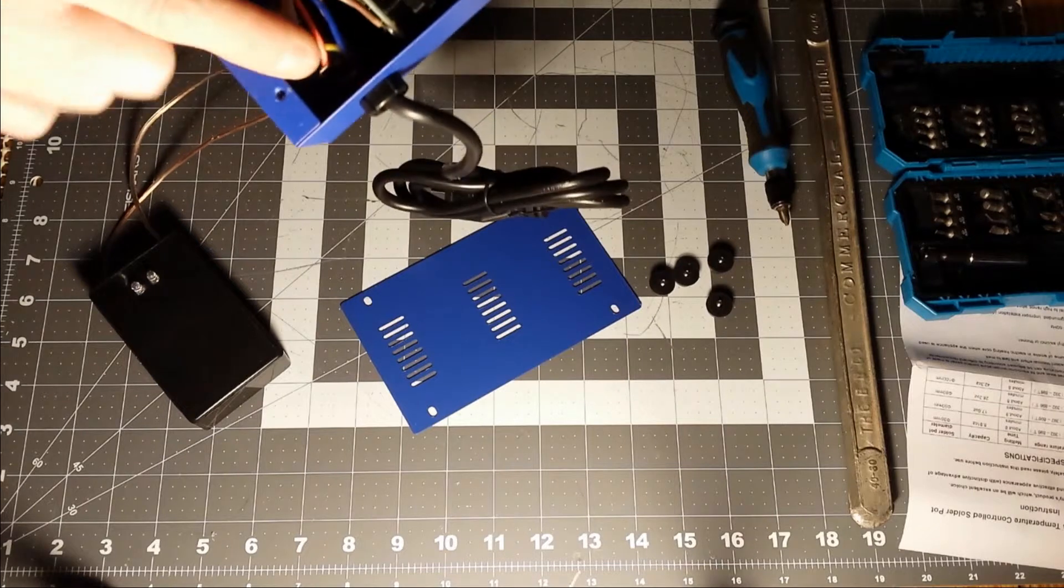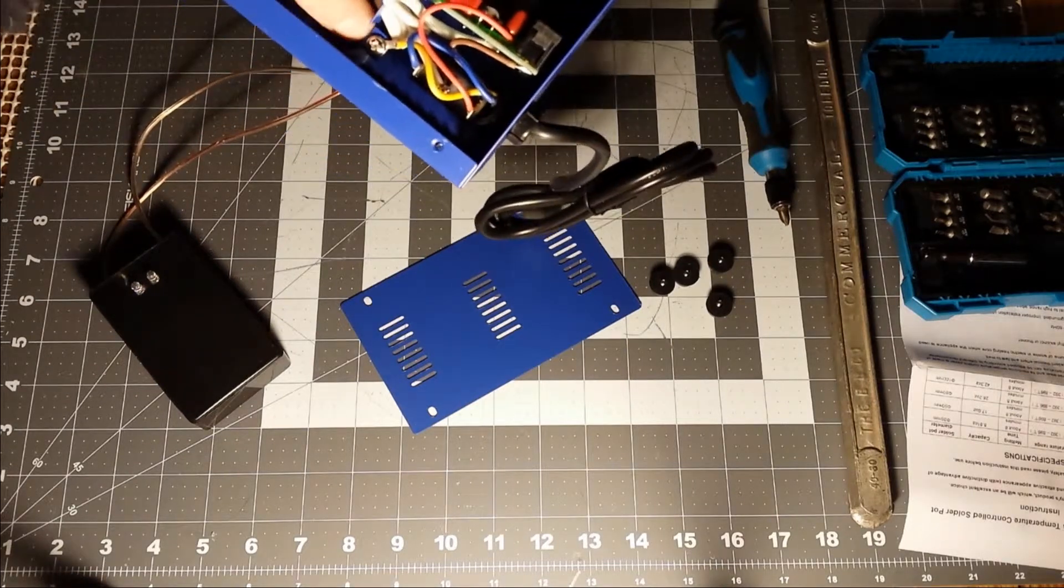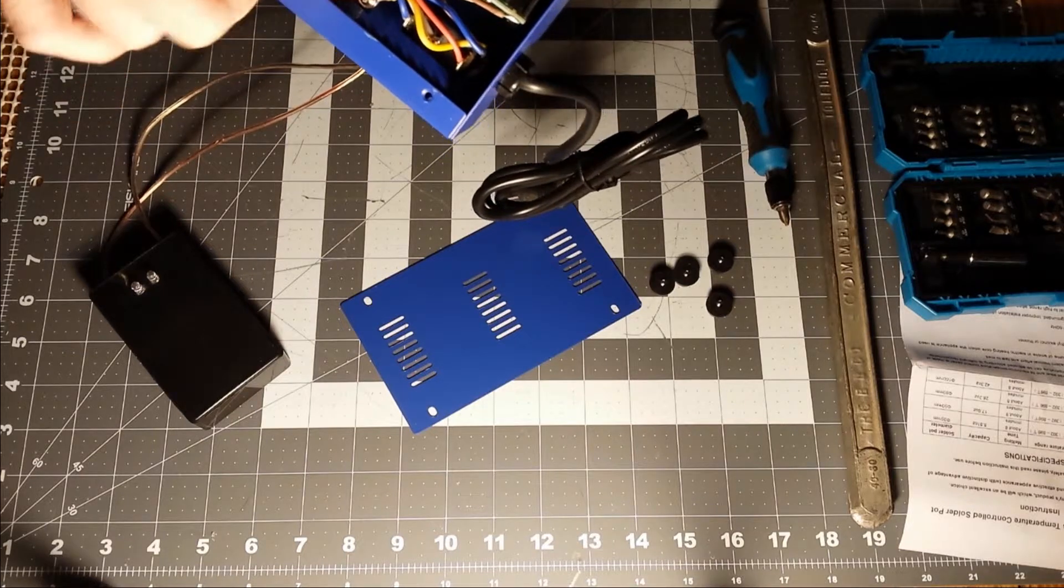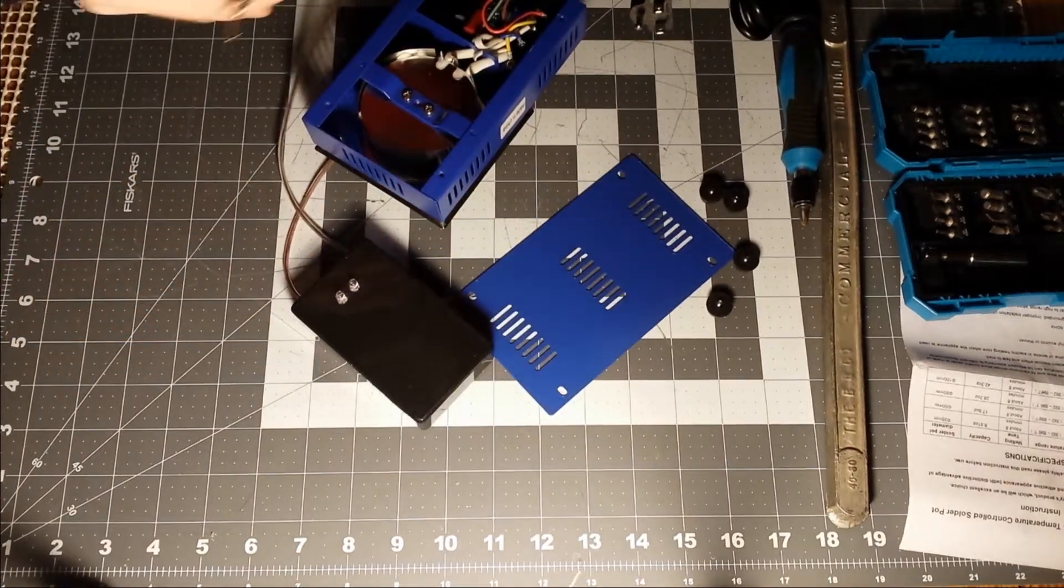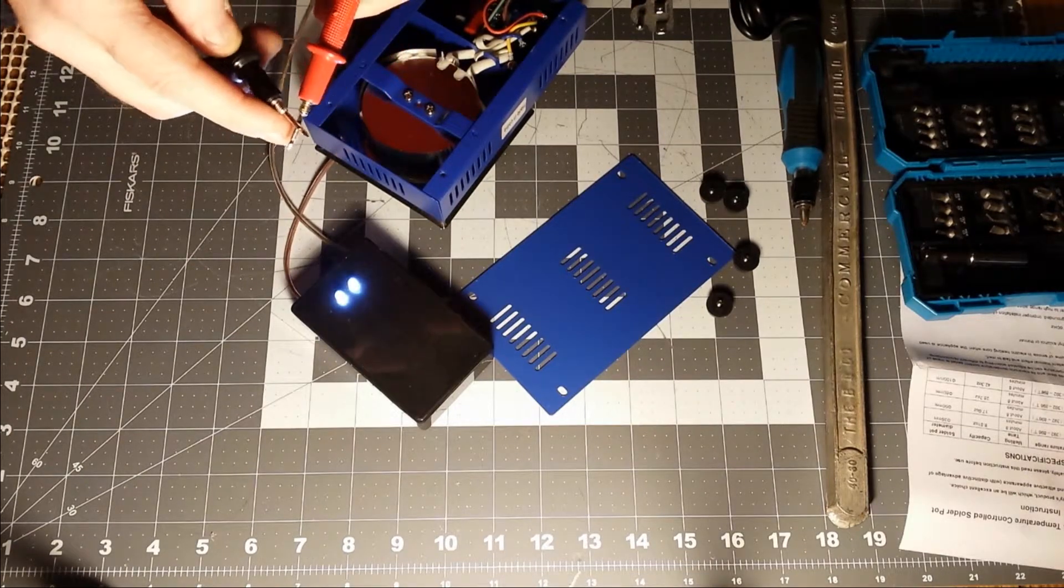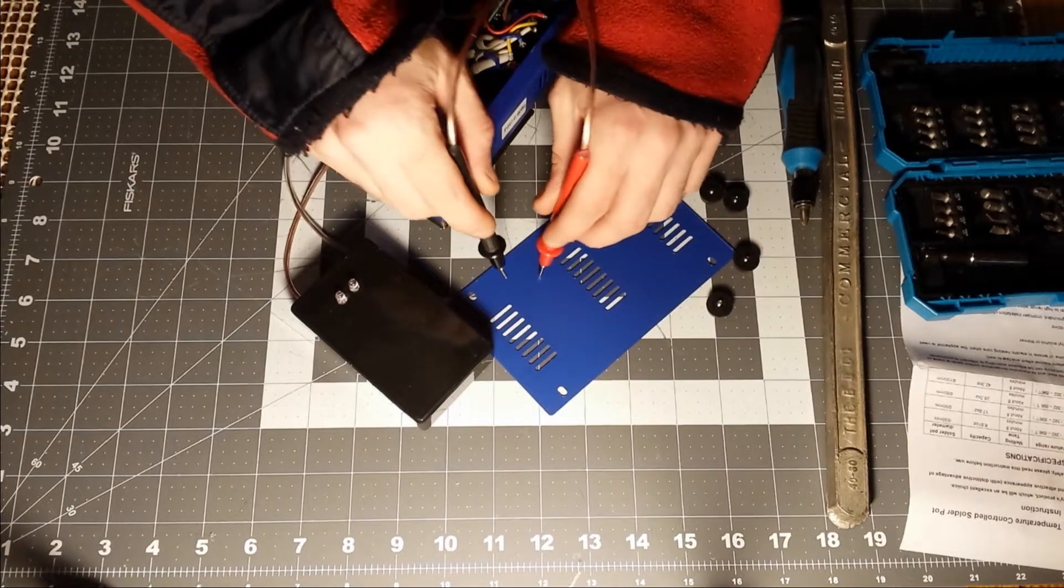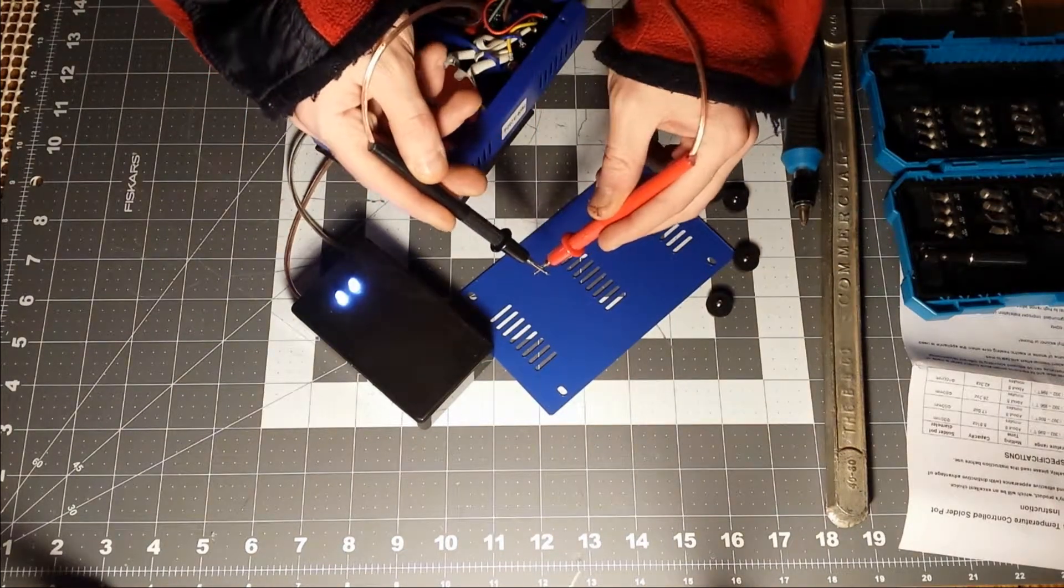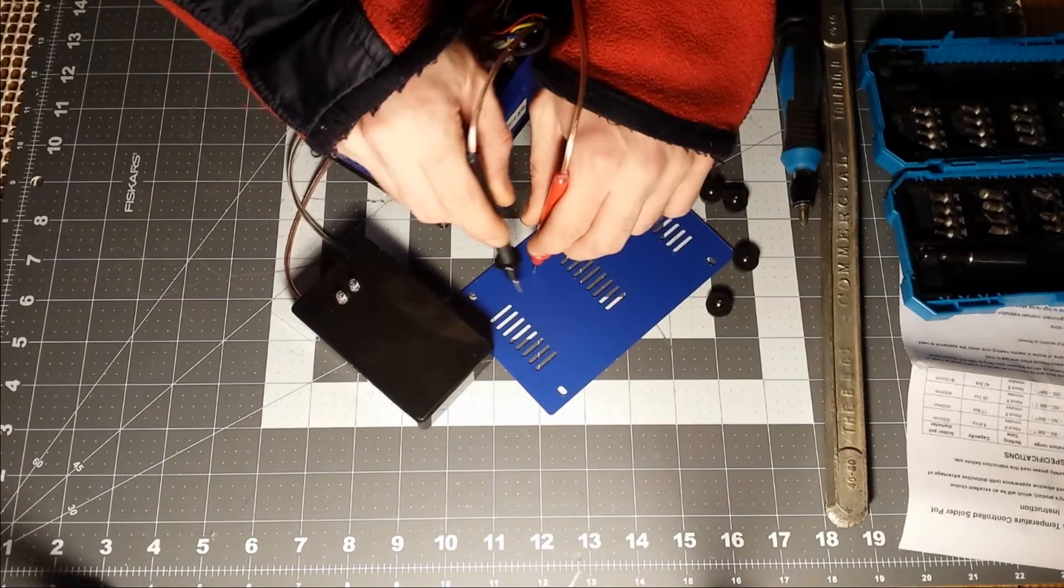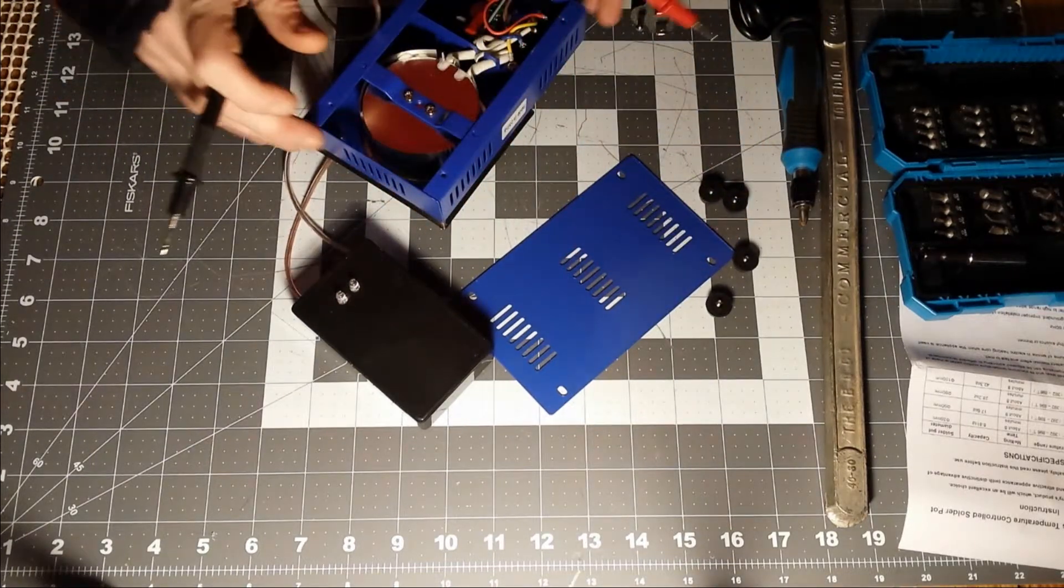The ground wire is yellow here, and it's screwed on to this metal. But the problem is, they didn't scratch away the paint. With my little homemade continuity tester here, the probes touch, and the light comes on. And you can see, this metal, nothing. If I touch the probes together, it's on. If I touch two spots on the metal, nothing. That paint is definitely not conductive.